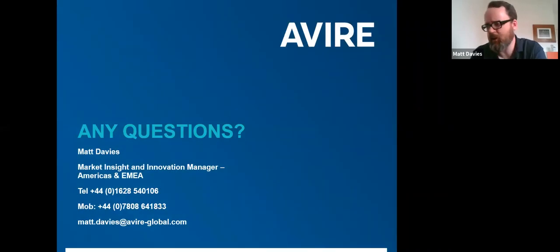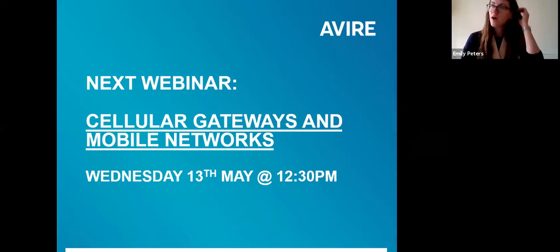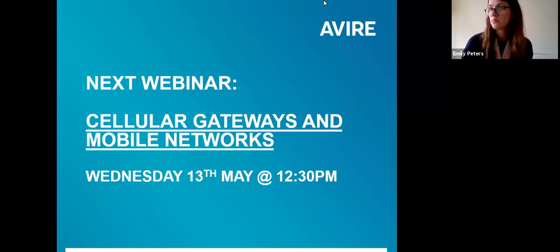So that's a whirlwind tour of EN81-28. Moving on to questions: how long will the backup battery on the Memcom and DCP work in the event of a power cut, how often do they need changing, and can people be alerted remotely? We certify our battery backups in line with EN81-28. From lab testing, a Memcom with its lead-acid battery gives around four hours, and the DCP with its LiPo battery comes in around the three-hour mark. Our batteries typically need to be replaced every three years, and this information can be notified through our monitoring platform via Hub. If there's a failure before that time, a technical call will automatically be placed.